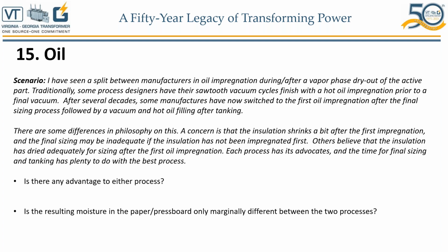So how do you take that surface moisture out? After you perform tanking, you put the cover on and weld the cover. Now you're going to go under vacuum again. At that time, just vacuum may not be enough, especially for large transformers. So some suppliers, some manufacturers, do hot oil spraying even after tanking the active part.